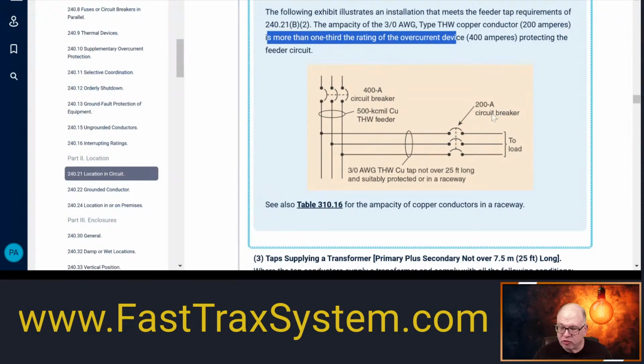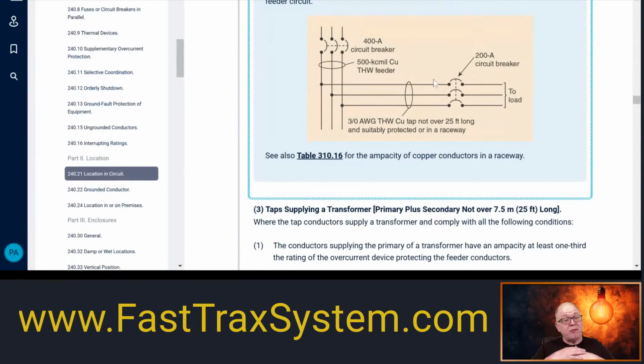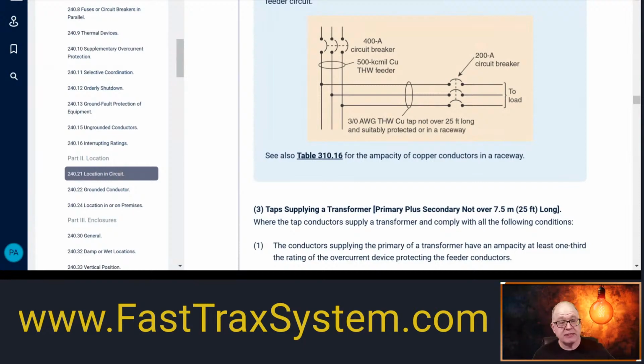All right? So this is a 200 amp device. It met the rules. This conductor is rated equal to or greater than the overcurrent device that it connects into. That rule is met. It is at least a third of the rating of the protection ahead of it on the feeder. Yep. It is. It's 200 amp rated, and all we needed was 133, so we're good. But because it's a 200 amp device, because you've calculated the load, you knew what you needed to have. So that means that these conductors right here are the tap conductors. Remember, you can't use the next size up rule. They have to be fully sized for the device that they're terminating into, right? And that is, in a nutshell, the simplicity of the 25-foot tap rule. Pretty straightforward and gets used literally every day.